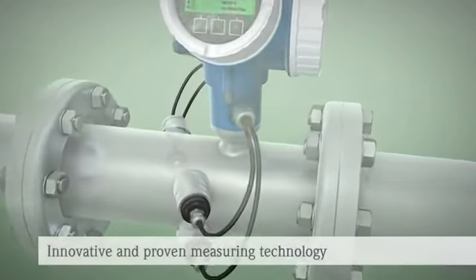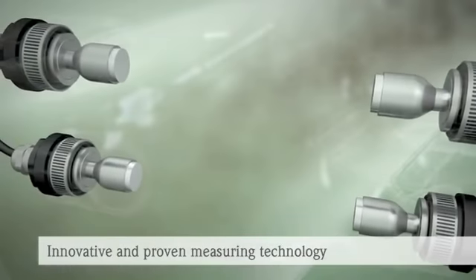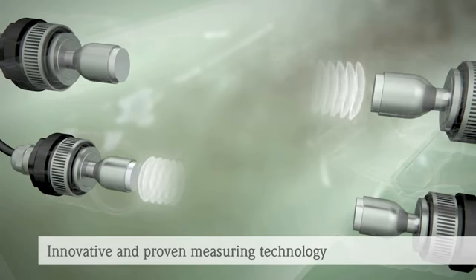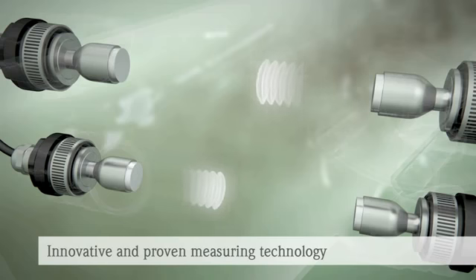Inside the ultrasonic flow meter, sensor pairs are fitted across from each other in the measuring tube. Each individual sensor can alternately transmit and receive an ultrasonic signal. In doing so, the transit times of these signals are measured along with the speed of sound.